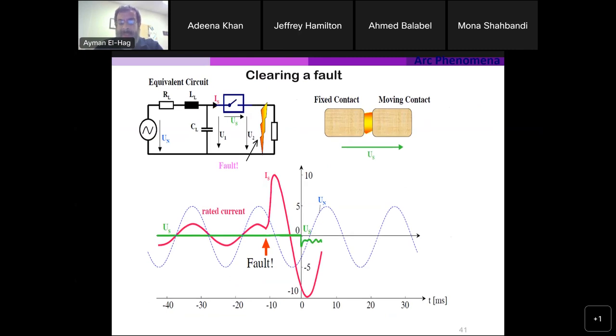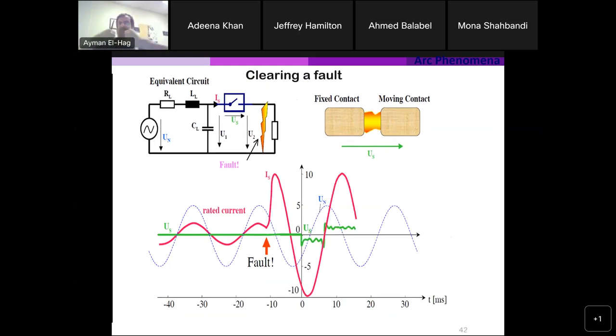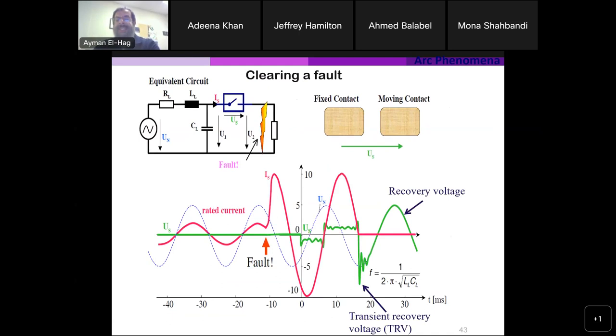Now we open. Once it opens, you will have some arcing, because as we open the breaker, the distance starts at zero between the two poles of the breaker, and as we start to move it's still very small. One side is energized, one is not, so you will have ionization and an arc between the two moving contacts of your breaker. So the voltage here will not be zero. It will be the resistance of the arc times the current. It's a small value, but still there. By elongating more, the fault is still not cleared, so the fault current is there. And you see here the green line, we still have a voltage until it is completely cleared.